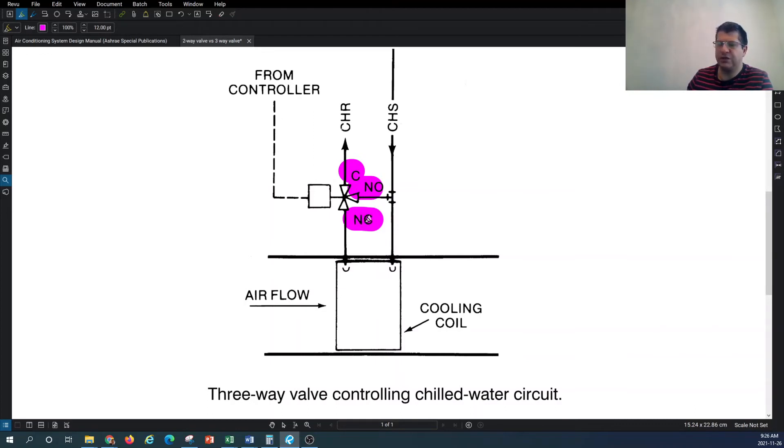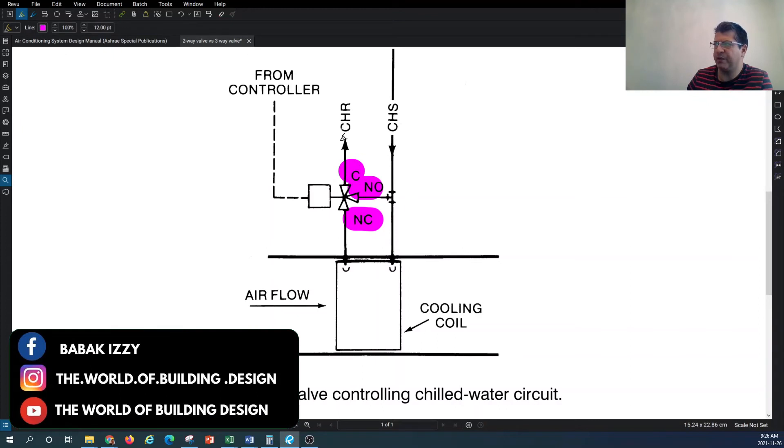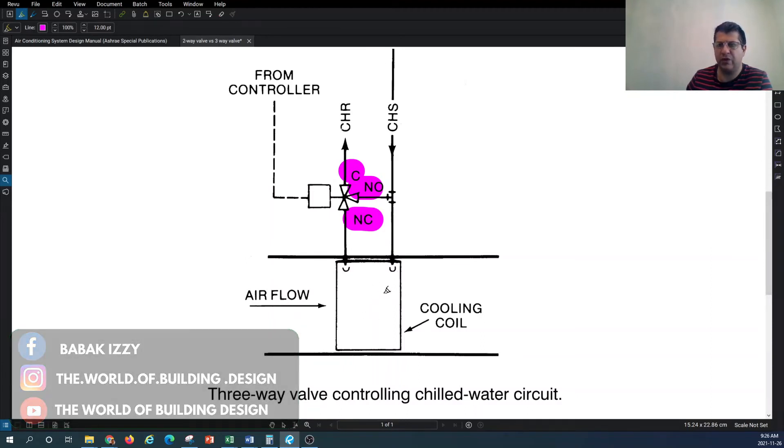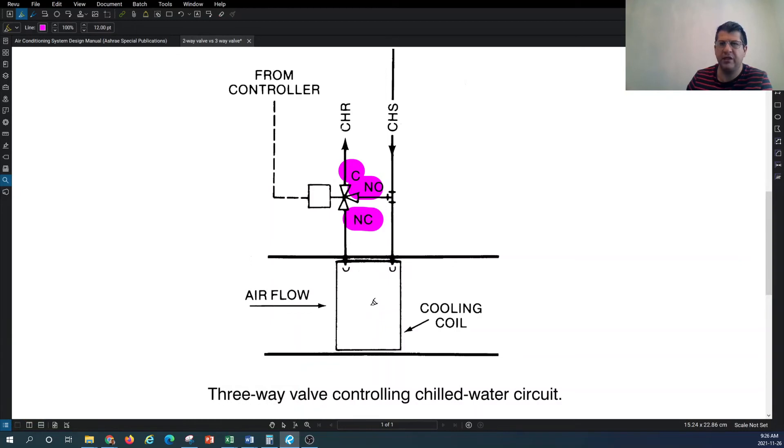If your normally closed valve position on the return side is open 20 percent, it means that the diverting portion of the valve is 80 percent open. This means 80 percent of the chilled water coming through this line is diverted back to the system, and only 20 percent comes into your cooling coil and circulates into your heating or cooling coil and provides the heat transfer effect.